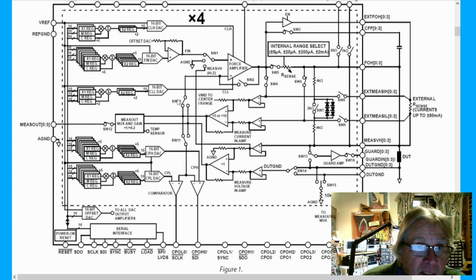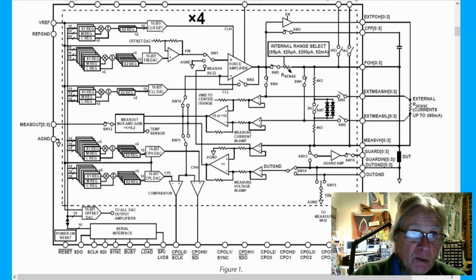In addition to the force DAC, there are 2 clamp DACs, clamp low and clamp high, and those are used to set clamp levels for either clamping current or clamping voltage, and those are also 16-bit DACs. And one of the unique things about this chip is that it has hardware offset and gain calibration for every range and for all 3 DACs. So if you look behind the force DAC, for example, you'll see 6 X2 registers, 6 X1 registers, 6 M registers, and 6 C registers. The X1 is what you use to set the voltage or the current, and there's 6 of them for the 6 ranges, 1 voltage range and 5 current ranges.